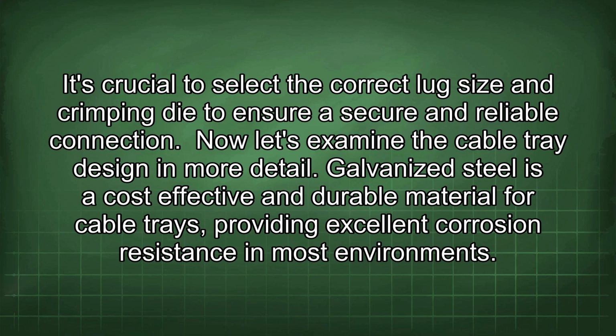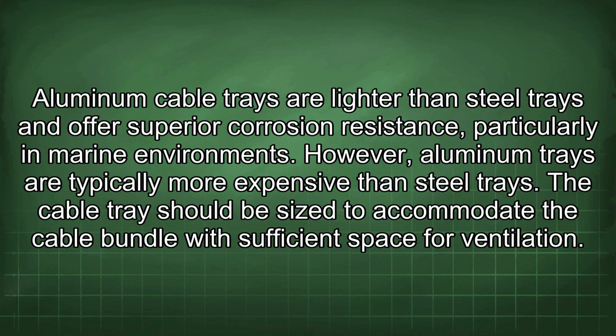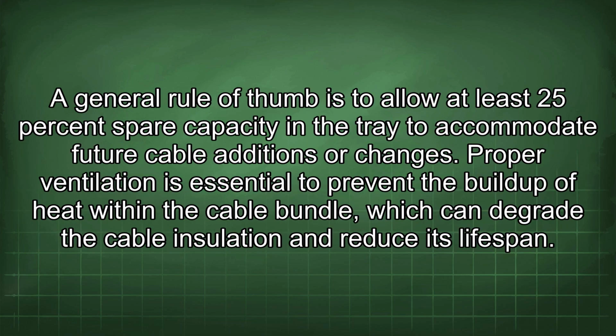Galvanized steel is a cost-effective and durable material for cable trays, providing excellent corrosion resistance in most environments. Aluminum cable trays are lighter than steel trays and offer superior corrosion resistance, particularly in marine environments. However, aluminum trays are typically more expensive than steel trays. The cable tray should be sized to accommodate the cable bundle with sufficient space for ventilation. A general rule of thumb is to allow at least 25% spare capacity in the tray to accommodate future cable additions or changes. Proper ventilation is essential to prevent the buildup of heat within the cable bundle, which can degrade the cable insulation and reduce its lifespan.